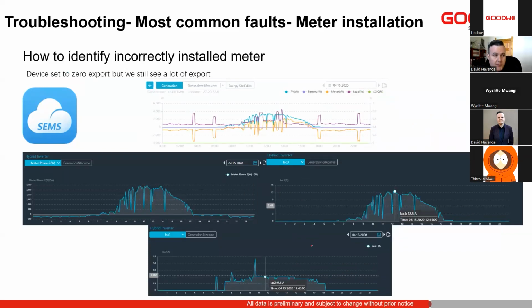Here's a nice example of a customer who had a phase rotation error. They rectified the phase rotation error. We then left the site, zero exports enabled. It shouldn't be exporting to the grid. The customer then phoned and complained and said the inverter is exporting. Zero exports enabled. Why is it doing this?